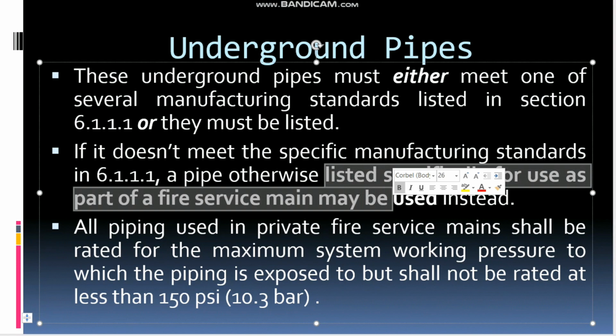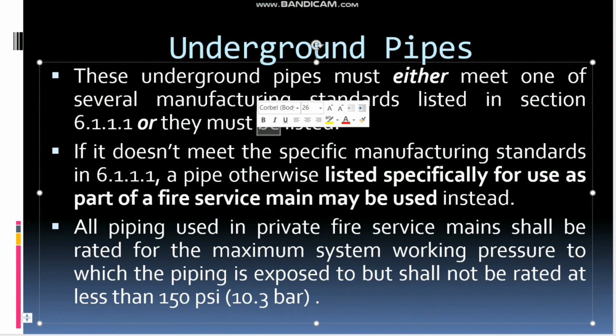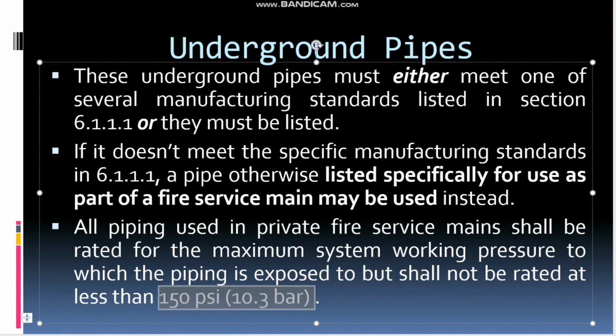If you see the jockey pump or pressure maintenance pump we use with the fire pumps, there is no requirement that the jockey pump should be listed for fire service. That can be listed for water supply also, and we can use it as a firefighting jockey pump or pressure maintenance pump. So there is that option, but if you are not following these pipes from the above table, then it has to be listed, and listed means again only for the fire service main. And coming to the third point, the pressure rating should be minimum 10.3 bar or 150 psi for the underground pipe.